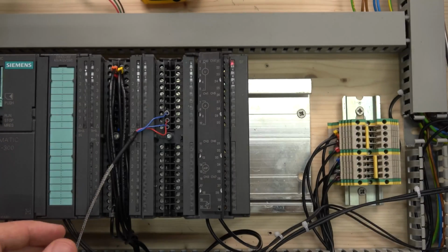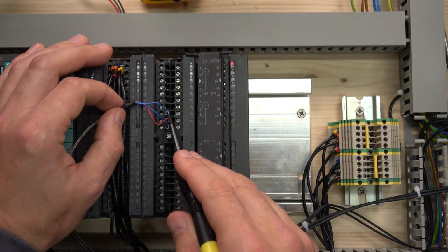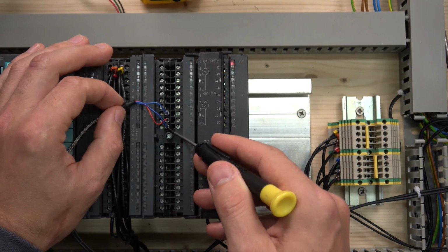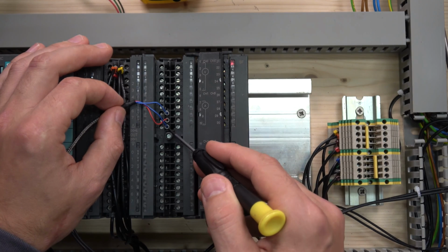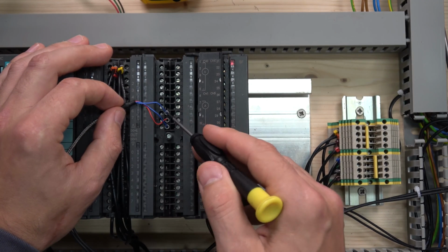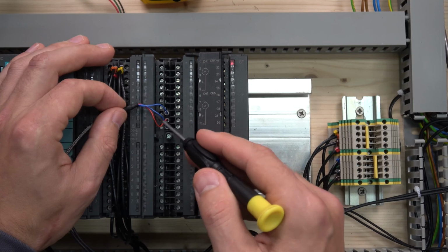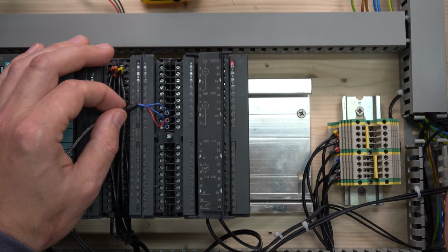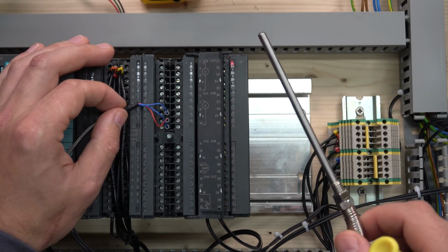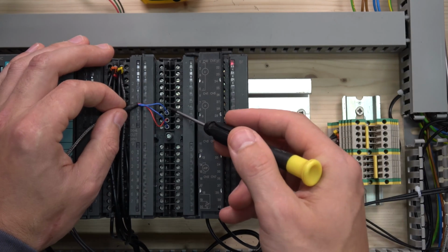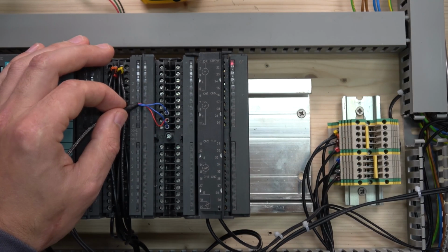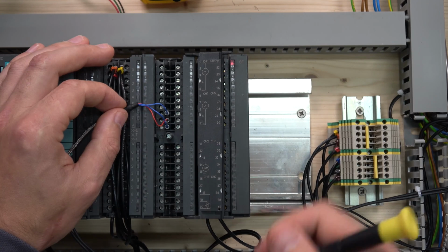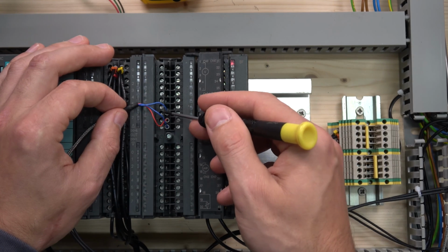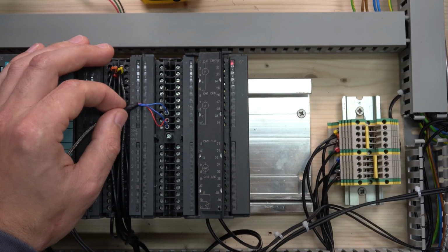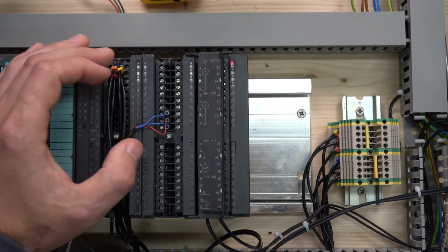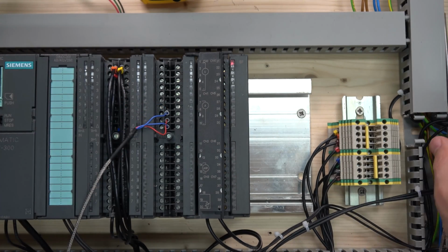So this is what we did, as you can see. Red is a plus, and then you can see there would be a bridge for the 2-wire. It's just got another wire coming out, literally joined up inside the actual probe itself. I'm not sure why they do it like that, but it is what it is, creating a 3-wire. So in our case, 8 and 10 are joined together, and 9 is our plus. So that's pretty much the temperature probe wired in.